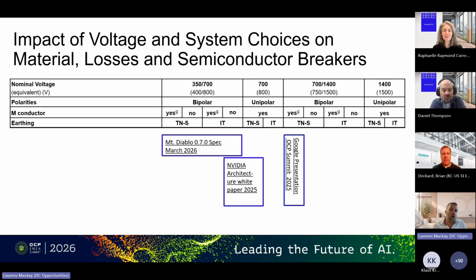So we have been making this — there's a lot of combinations there, and we have made a very comprehensive table of different characteristics we can be looking at. In this table, this is just the headline. On the top row you see the nominal voltages: 350/700 volts, 700/1400, and 1400 volt, which are the standardized DC voltages now being internationally standardized globally in IEC. Underneath we have 400/800 volts, and 750/1500 volts, which have been used in the data center discussions.